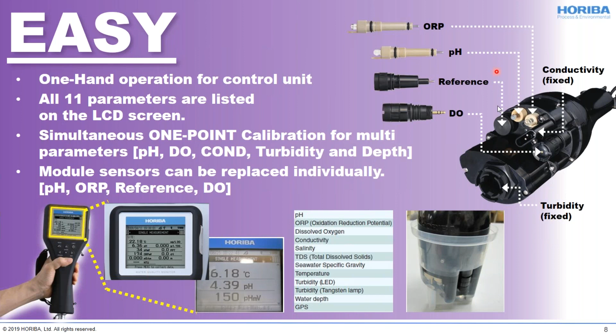This is the detail about one-point calibration by pH4 standard solution. pH, conductivity, and turbidity are calibrated with the values listed here, and the DO (dissolved oxygen) and depth sensors are located where they are not immersed in the solution, designed by this special beaker, so these are calibrated in ambient condition. You can see the location of the dissolved oxygen sensor here, and this yellow part is going out of the beaker, so it is not immersed in the solution. By using just pH4 with this smart calibration beaker, you can get 5 parameters calibrated at one time. So it is very easy to operate.